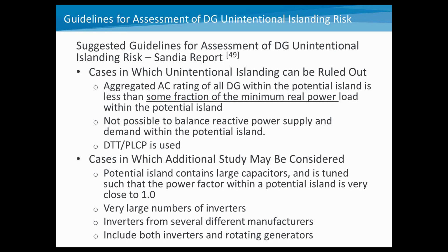Additionally, they said you should consider a closer study if the potential island contains large capacitors and is tuned to a power factor at which you could maintain the real and reactive power balance inside that island. That's one thing. If you have a very large number of inverters, so if all of a sudden you're looking at 100 or 1,000 inverters inside a particular area, that may warrant additional consideration. Also, if inverters are from a variety of different manufacturers, oftentimes you don't know exactly what type of anti-islanding technique they're using in their systems. Of course, you can ask the manufacturer to provide more information on that. And if you have potential islands that may include inverters and rotating synchronous generators, then you probably want to take a closer look, because the rotating generators potentially could trick the inverters to stay on longer than you would think. But again, these are guidelines to help someone assess the actual probability of islanding.